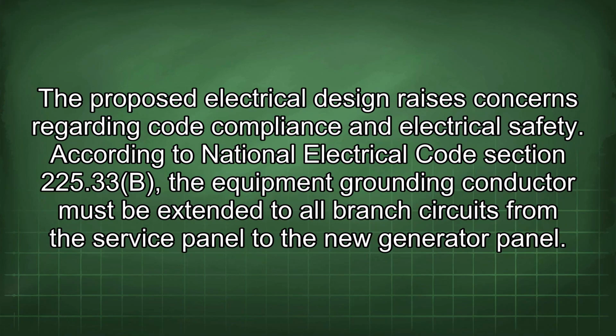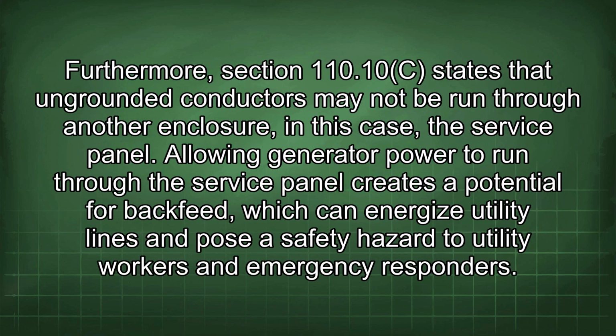The proposed electrical design raises concerns regarding code compliance and electrical safety. According to National Electrical Code Section 225.33(b), the equipment grounding conductor must be extended to all branch circuits from the service panel to the new generator panel. Furthermore, Section 110.10(c) states that ungrounded conductors may not be run through another enclosure, in this case, the service panel. Allowing generator power to run through the service panel creates a potential for backfeed, which can energize utility lines and pose a safety hazard to utility workers and emergency responders.